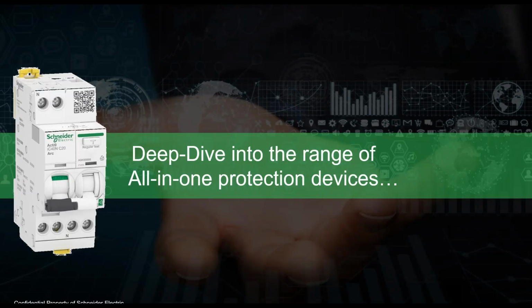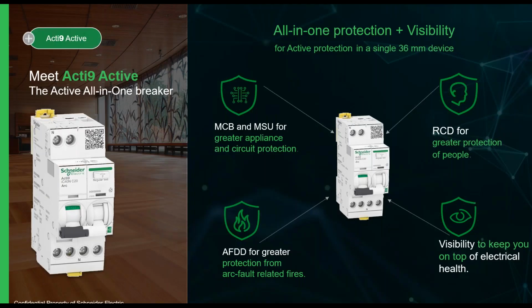So let's have a little deep dive into the range of the all-in-one protection device. So this is what it looks like. It's got built into this single device all of these fantastic functions for protection. So we've got what we would see as traditional circuit protection with the MCB, AFD, RCD, MSU. But then we've got that fantastic attribute of visibility that allows us to stay on top of the electrical health of the system. This is how you could term the Fitbit or iWatch to your building.